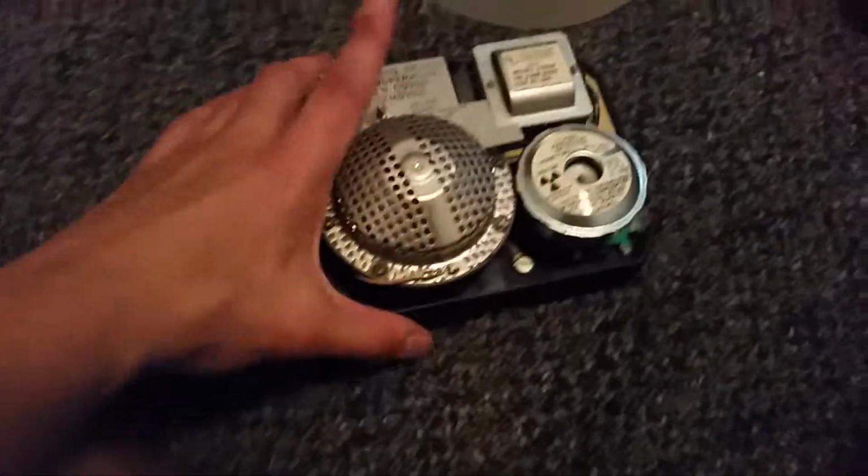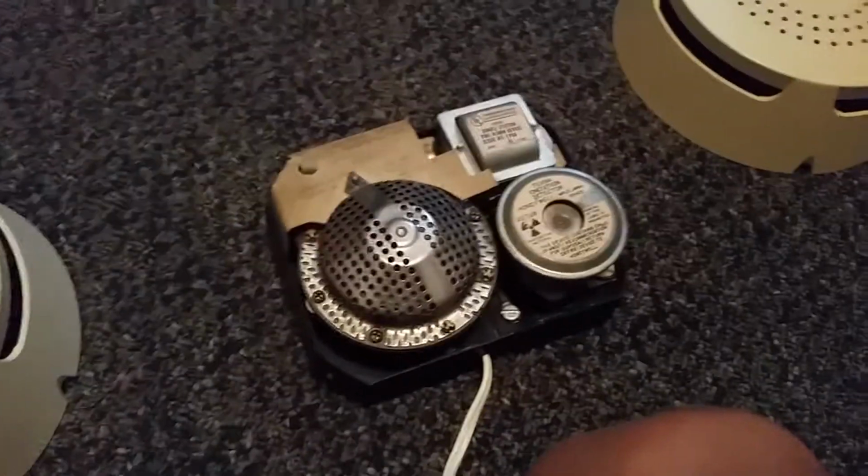And you can see that it says right there on the transformer, multiple station fire alarm device. This one says single station fire alarm device, but that's because this one has interconnecting possibilities. They both have the same sensitivity adjustment knob. The placement's a little bit different. This one's down here and this one it's up here. They're actually both from 1976, but I think this one is newer, considerably newer. They probably upgraded between that one and this one. That one was only designed for single station purposes.